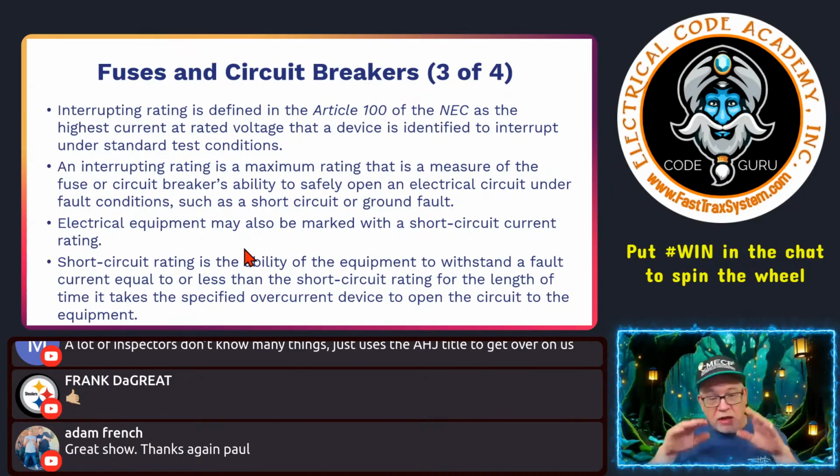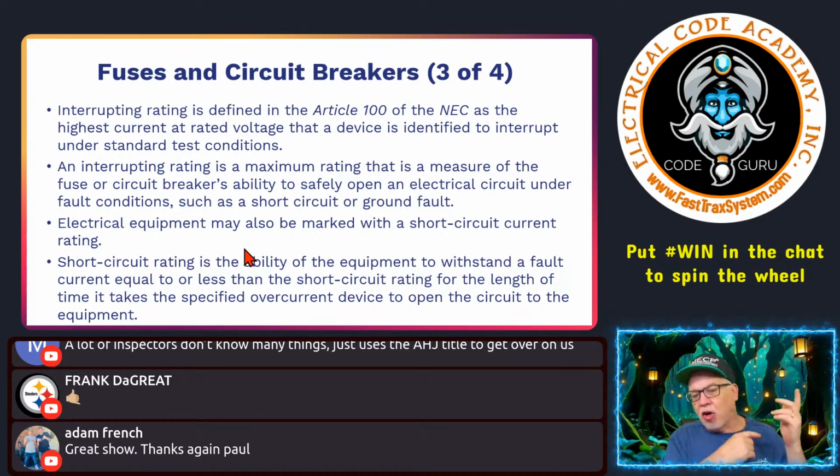So usually this is done from the manufacturers. You'll get a breaker with an AIC rating, and then you'll get a short circuit rating for the equipment. Let's say it's 22,000 SCCR, and then the breaker will be 22,000 at least, interrupting rating. And again, everything works happy. And then all you have to do is make sure that you know what your available fault current is from the utility down. Usually they may give it to you at the secondary of the transformer.